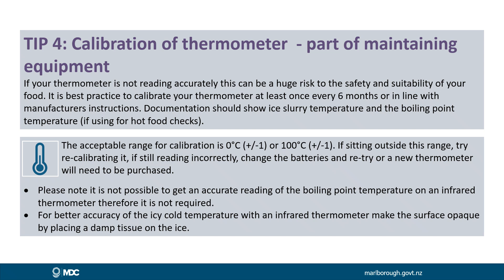Please note it is not possible to get an accurate reading of the boiling point temperature on an infrared thermometer, therefore it is not required. For better accuracy of the icy cold temperature with an infrared thermometer, make the surface opaque by placing a damp tissue on the ice.